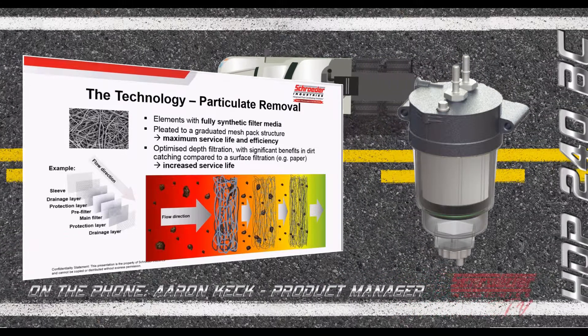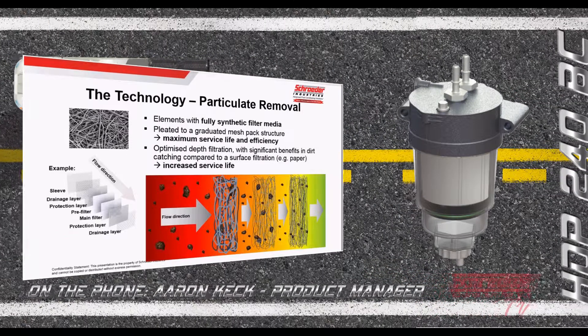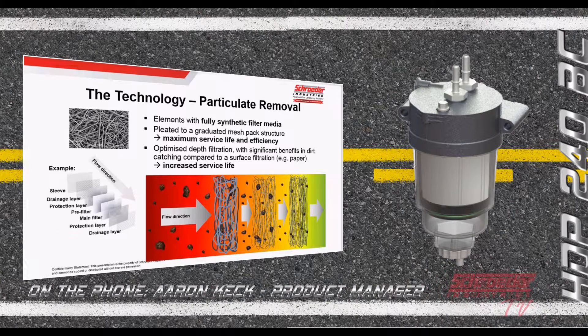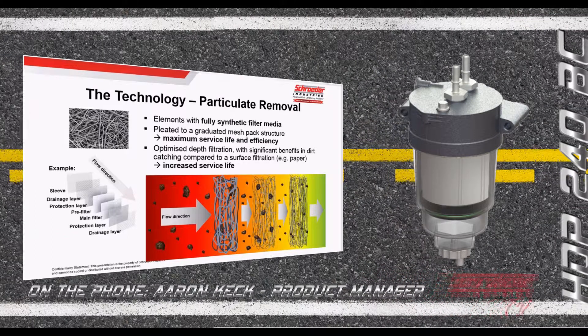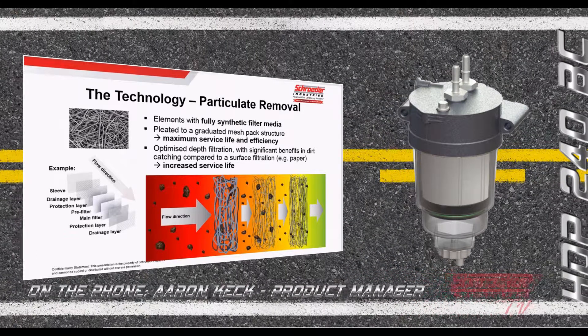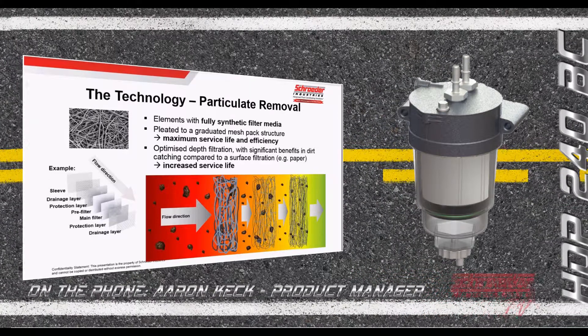That layered structure — starting with very coarse filtration, moving to medium density, then a very tight filtration layer — creates depth filtration that provides great benefits in performance, service life, and efficiency. Most importantly, it dramatically improves dirt-holding capacity compared to similar or previously used cellulose medias in the industry.